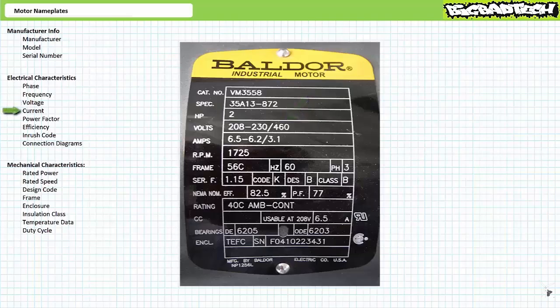The current entry on a motor nameplate specifies the amount of current drawn per phase when the motor is operated at the rated condition. As with the voltage entry, dual voltage motors often have two entries in the current field, one for the low voltage configuration and another for the high voltage configuration. In our previous example, this 2-horsepower motor draws 6.5 amps per phase in the 208-volt low voltage configuration, 6.2 amps in the 230-volt low voltage configuration, and only 3.1 amps per phase in the high voltage 460-volt configuration.